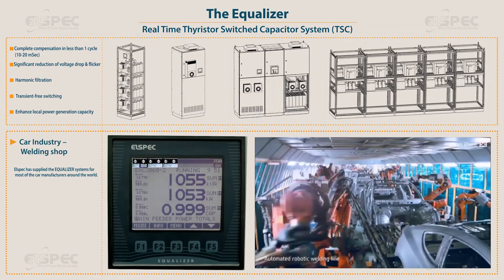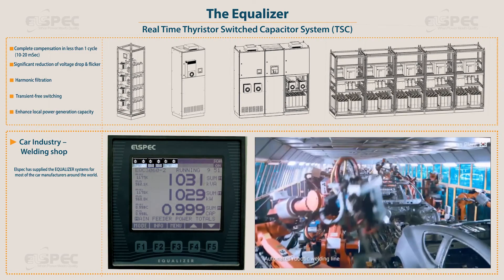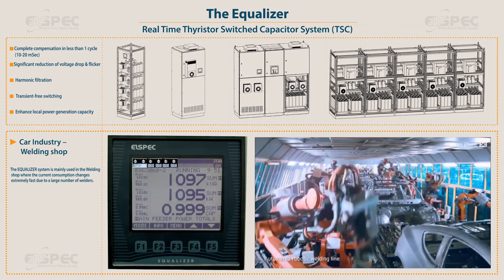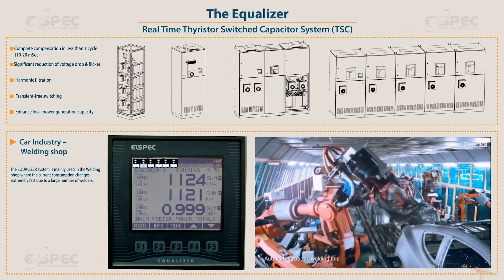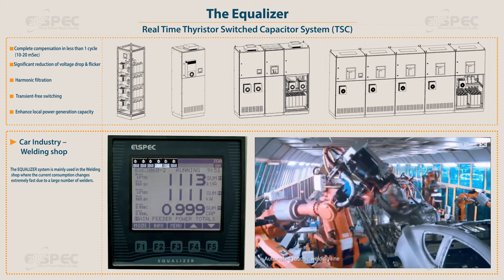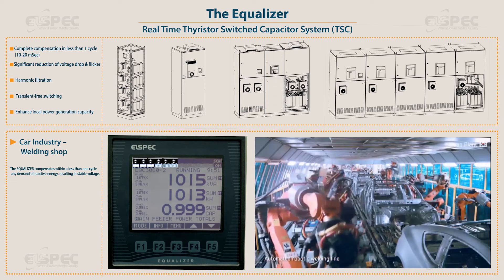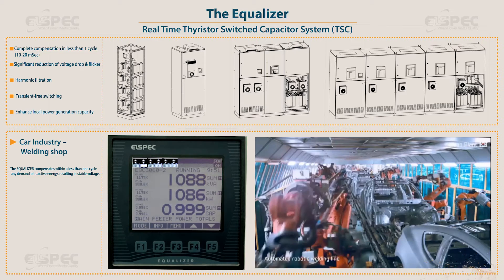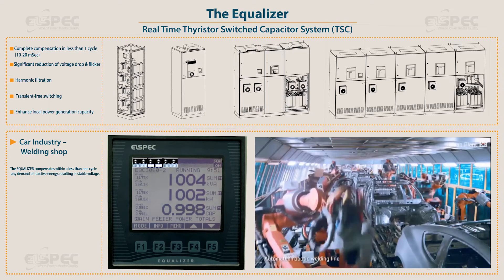Elspec has supplied the equalizer systems for most of the car manufacturers around the world. The equalizer system is mainly used in the welding shop where the current consumption changes extremely fast due to a large number of welders. The equalizer compensates within less than one cycle any demand of reactive energy, resulting in stable voltage.